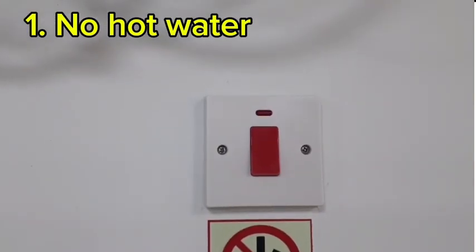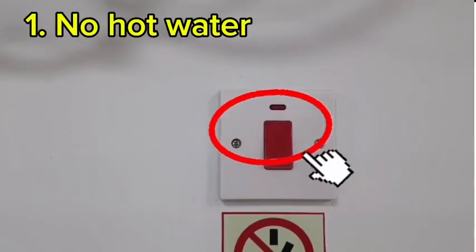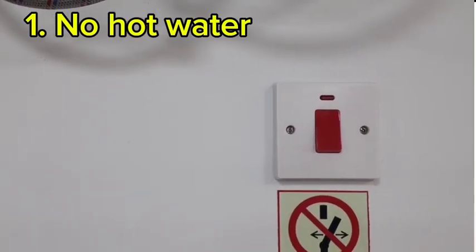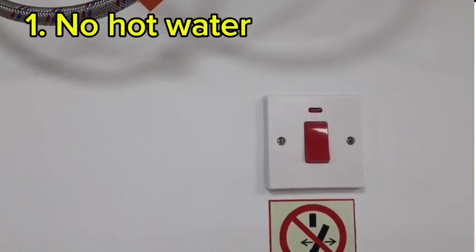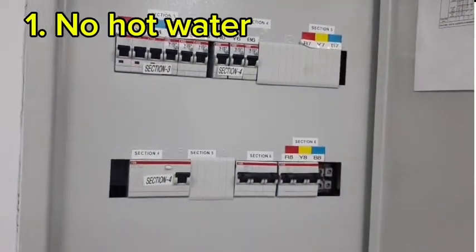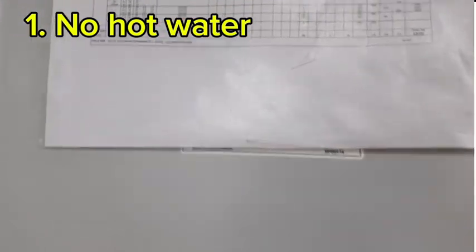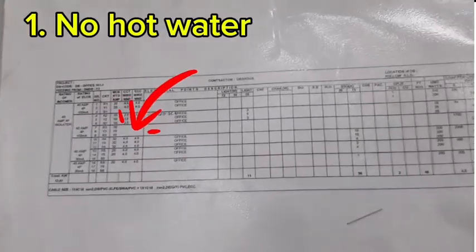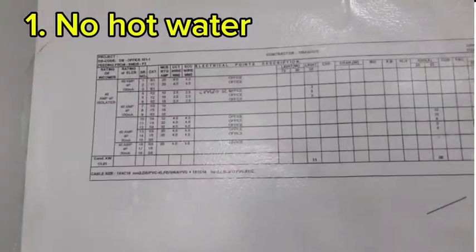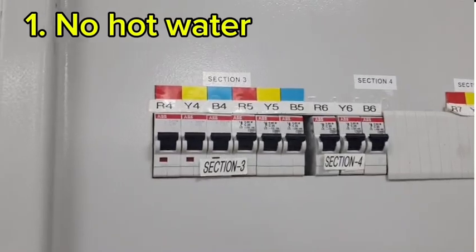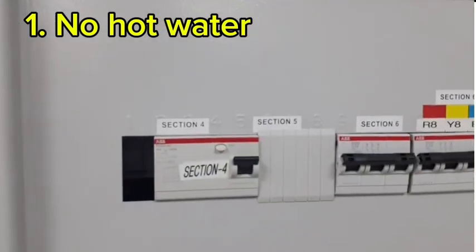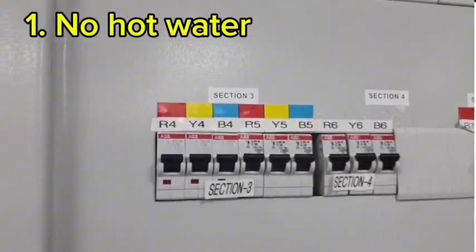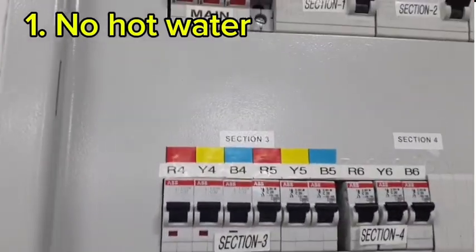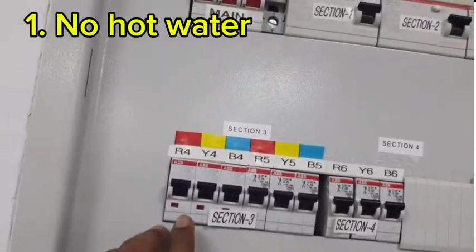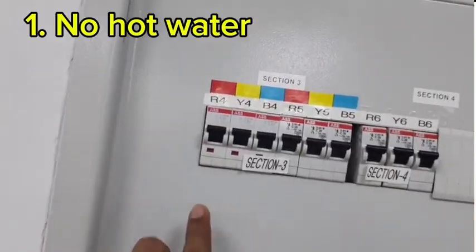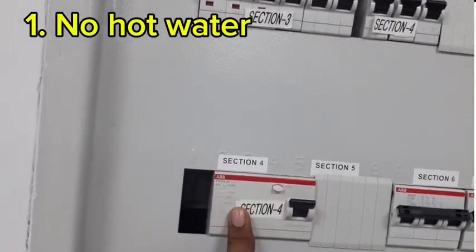Second, if there is no power supply in the switch, that means there is no power coming from the electrical distribution board. So I have reached near the electrical distribution board. Go through the load schedule, you will find the circuit number. Once you have gone through the load schedule, you will find an MCB or RCCB. If your water heater has tripped, there are several causes such as overload and short circuit. If there is any overload or short circuit, your MCB will trip. If there is any earth leakage, then your RCCB will trip.